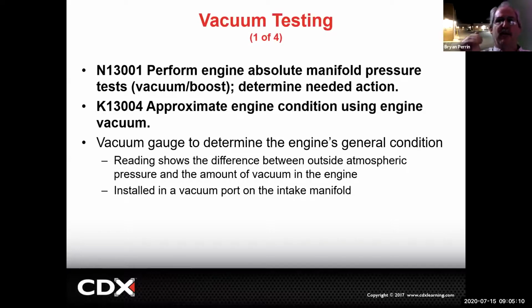Vacuum is a mechanical function. So vacuum is what's called a high-level test. A vacuum test will tell me if there's something wrong. It doesn't necessarily tell me everything's good, but it'll tell me if I have a problem. And it's a very easy test to do. And that's why people do it.